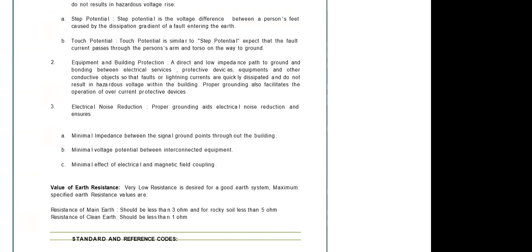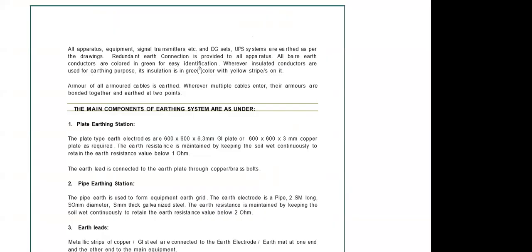The value of earth resistance generally followed is less than 3 ohm, and for rocky soil it is less than 5 ohm. Clean earth should be less than 1 ohm, but for all practical purposes, generally we follow an earthing of less than 1 ohm in both cases. It is to be kept in mind that all apparatus, equipment, signal transmitters, etc., each and every component has to be earthed. It cannot be said that this equipment or this drive is not required to be earthed. Each and every equipment used in the electrical circuit, where any cable or bus duct is terminated, requires a solid earthing. So we cannot say, okay, this is small equipment, no earthing is needed. It is not like that.